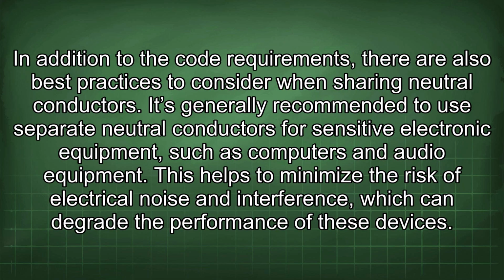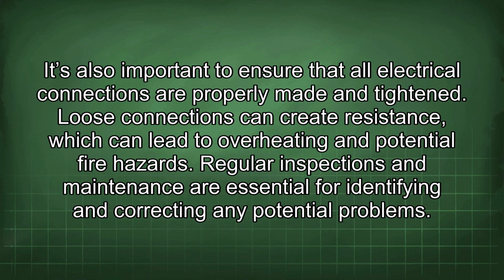In addition to the code requirements, there are also best practices to consider when sharing neutral conductors. It is generally recommended to use separate neutral conductors for sensitive electronic equipment, such as computers and audio equipment. This helps to minimize the risk of electrical noise and interference, which can degrade the performance of these devices. It's also important to ensure that all electrical connections are properly made and tightened. Loose connections can create resistance, which can lead to overheating and potential fire hazards. Regular inspections and maintenance are essential for identifying and correcting any potential problems.